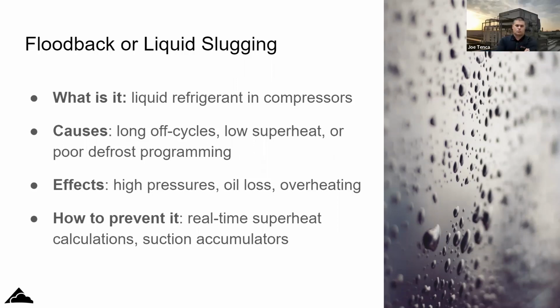Yeah, I think most refrigeration systems now have control systems, and they have sensors on, even if it's just one sensor on the suction header. There's enough information there to see what the system's doing throughout the day and night. And I mean, it's there for a reason. One thing I've always found is sometimes the suction header sensors aren't in the ideal location, and they're on the far end, or they're in an obscure part of the header where there's really no systems. So sometimes you can get some poor readings on those.